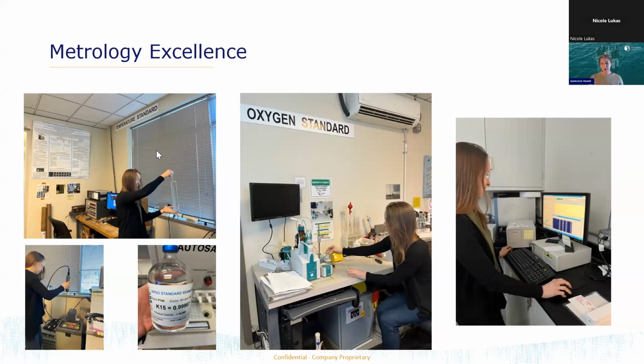And then throughout our calibration process, we actually draw water samples from the bath, and we will take those water samples and run them through the Guildline Autosal, and that's how we understand exactly what the salinity was during that time, and we back calculate to get the conductivity. So by changing the temperature overnight over the course of the calibration run, we also change the conductivity reading. And so we're able to grab different conductivity points and calibrate your conductivity sensors that way.